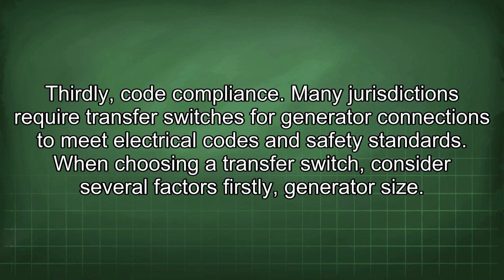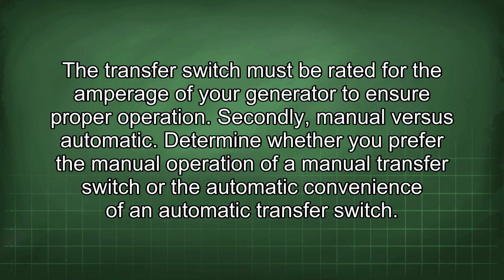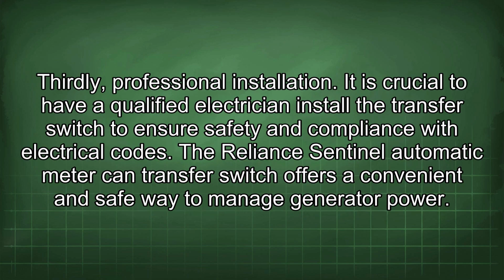When choosing a transfer switch, consider several factors. Firstly, generator size: the transfer switch must be rated for the amperage of your generator to ensure proper operation. Secondly, manual versus automatic: determine whether you prefer the manual operation of a manual transfer switch or the automatic convenience of an automatic transfer switch. Thirdly, professional installation: it is crucial to have a qualified electrician install the transfer switch to ensure safety and compliance with electrical codes.